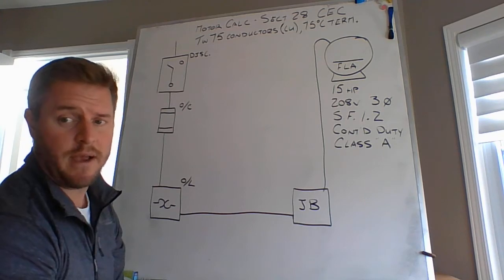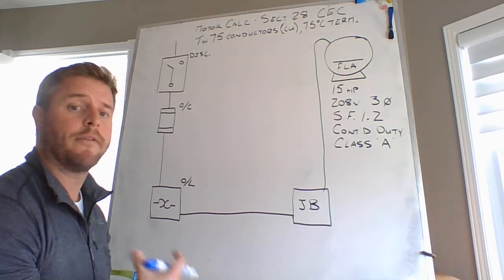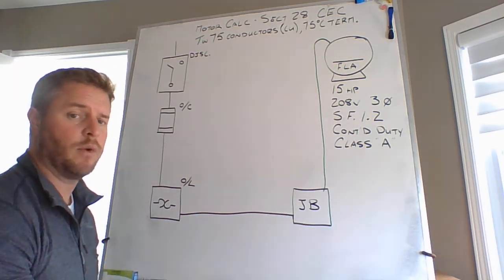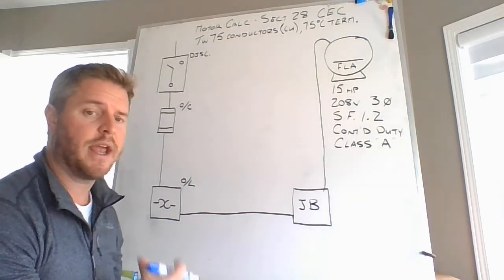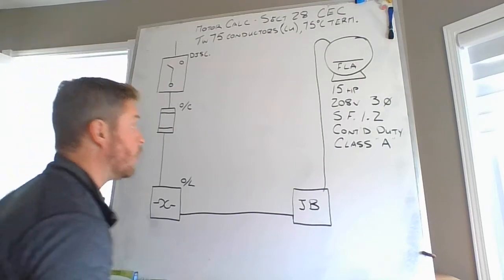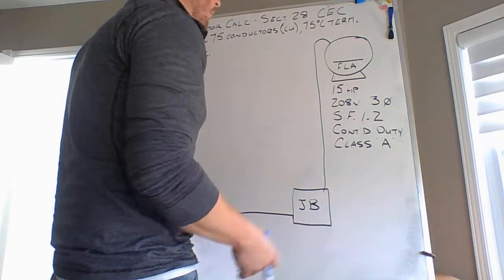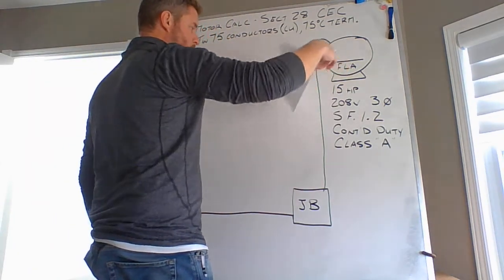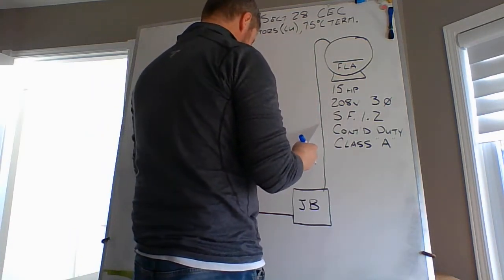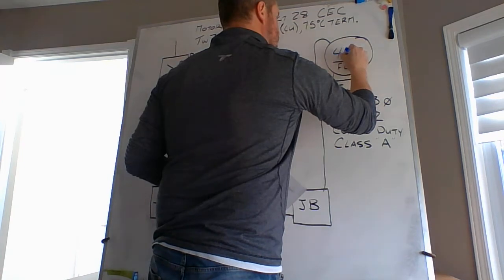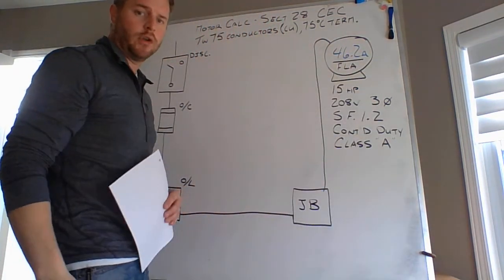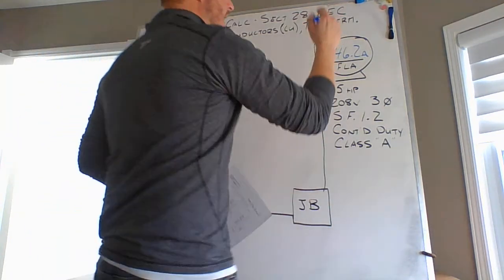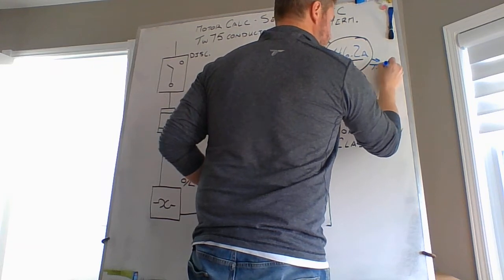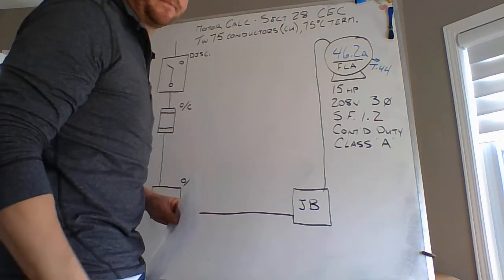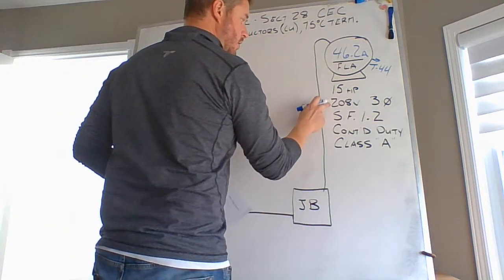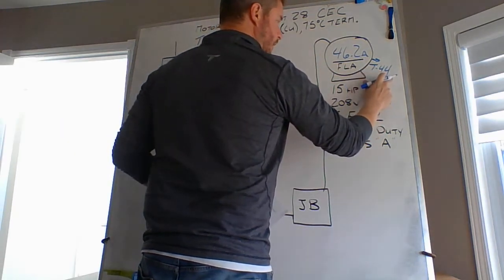At this point in time, my very first step is to calculate what my full load current rating is going to be. I know that I have a 15 horsepower motor connected to a 208 volt source and it's a 3-phase motor. So I can go right to Table 44 and find, under the 208 volt column, scrolling down on the far left hand side to 15 horsepower, that this motor is good for 46.2 amps FLA, full load current. 46.2 amps. I came up to that value from Table 44 for a 3-phase AC motor, based on the 15 horsepower, 208 volt, 3-phase.